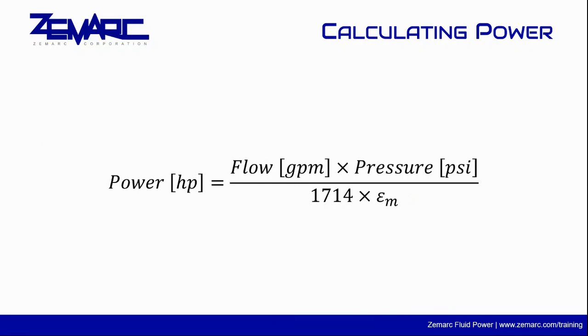To calculate power, you need to have a few different variables. The power required by a pump determines the minimum power rating of its motor. The pump's required power can be determined by the equation in this slide. As the pump's output flow and/or the pressure increases, so does its power draw.